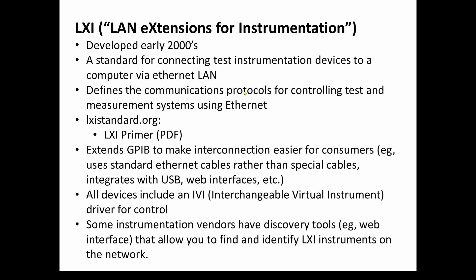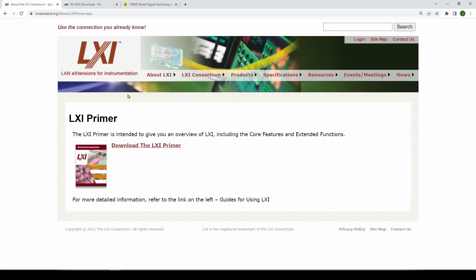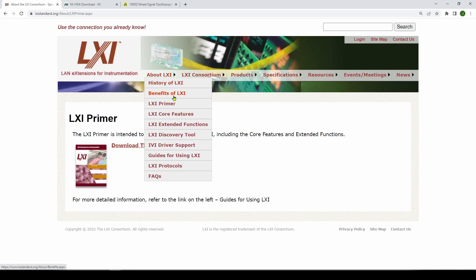LXI defines the communication protocols for controlling test and measurement systems using Ethernet. If you want to learn more, you can go to lxistandard.org. There's really good background information in what's called an LXI primer. The website has history of LXI, benefits, the LXI primer itself, and an LXI discovery tool — we're going to talk about that — as well as driver support and LXI protocols.